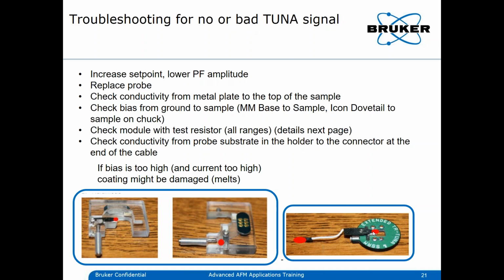Basically, you would measure here from the substrate, where at the very end is the cantilever. You don't have to measure from the cantilever, but the substrate bottom side is also coated with the same metal or conductive surface. And then to the end of the cable in between, the resistance should be 0. If you don't want to measure on the tip, you can also put a small sharp tweezer in here and just hold it down with a clamp, and then you would measure the same from the tweezer to the end of the cable. Again, the resistance should be 0.